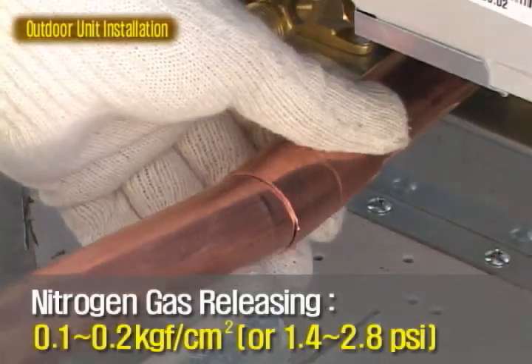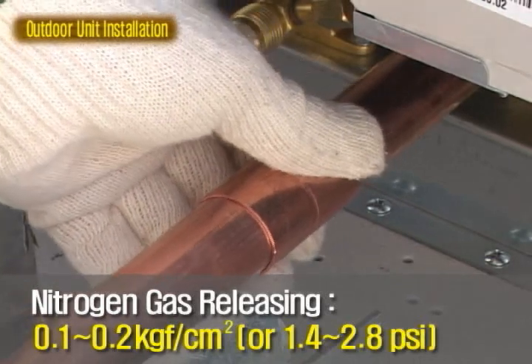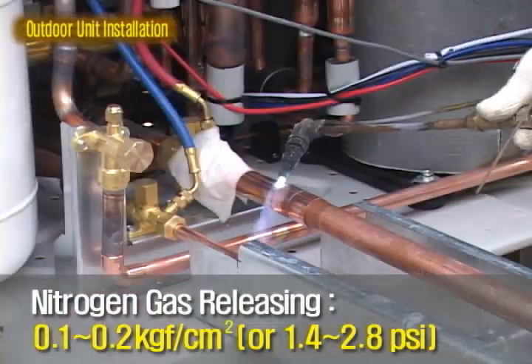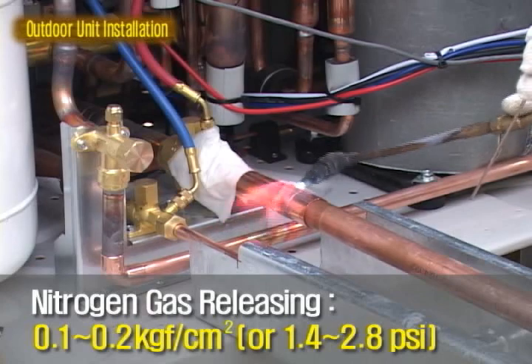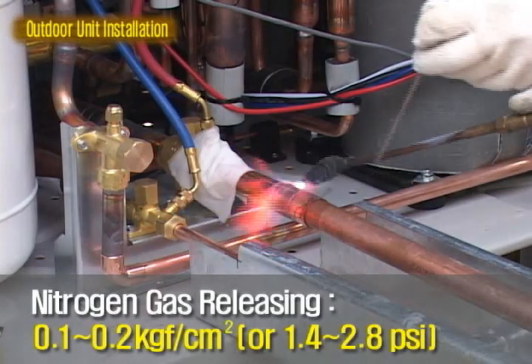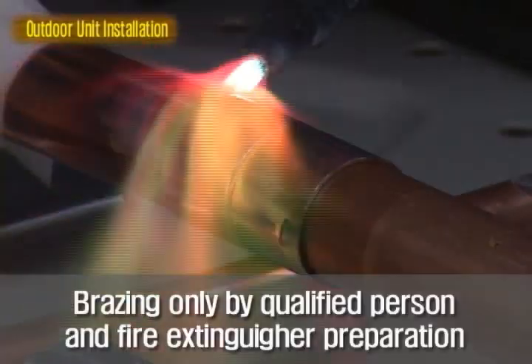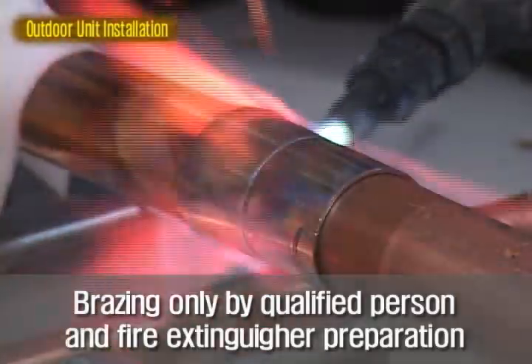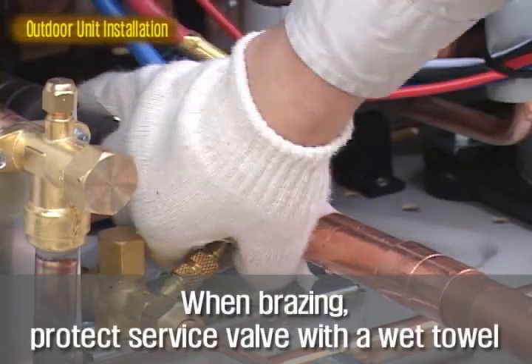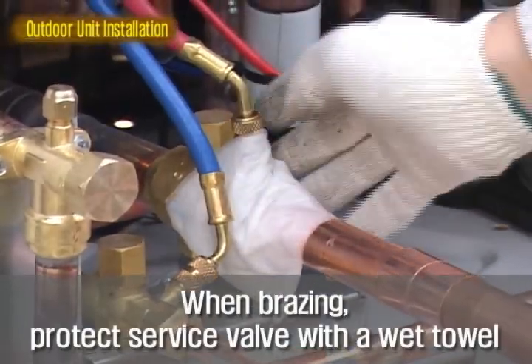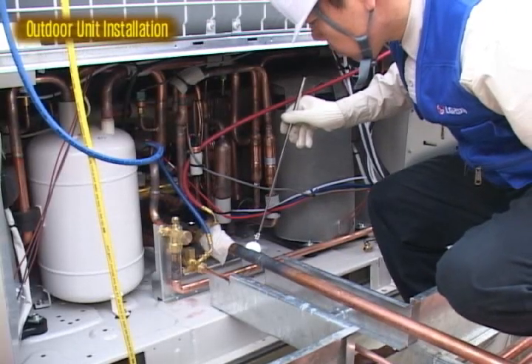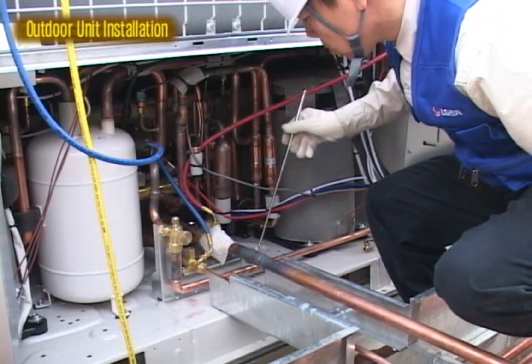To extend copper pipe with brazing, expand it for soft pipes or use sockets for straight hard pipes. And make sure the pipe is overlapped sufficiently. Brazing is done by the flow of melted solder into the overlapped pipe. During brazing, protect the service valve with wet towels and check the brazing state after finishing it.